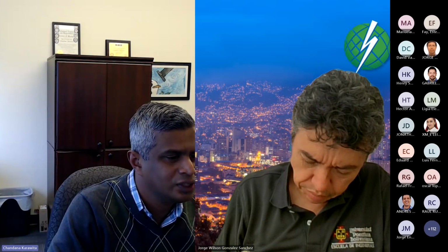And about the working group, Jorge, I mentioned that we have this new working group on the dynamic, active and reactive power supporting devices for VSC systems. I saw the previous presentation as well, the STATCOM with storage, grid forming STATCOMs. So in this working group, we will talk about AC/DC choppers and usage of synchronous condensers together with VSC systems and the STATCOMs, either for reactive power support or grid forming purposes. We will evaluate these feasibilities in the working group. It is B4.100. So I invite you to join the working group through your country's B4 representative. Please contact your country's B4 representative.